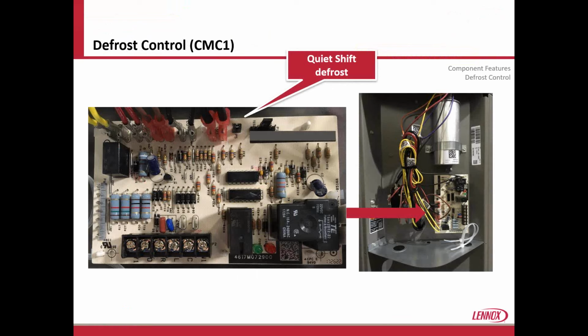All right, so our standard time and temperature board: all of our other units, including our package heat pumps, use a standard time and temperature control that you're used to out in the field. We have a quiet shift feature on it from the factory default, on pin jumper number 5. The jumper is in place, and that gives you a delayed defrost, a quiet shift type of operation. We have about a 30-second delay between the compressor shutting off and the reversing valve shifting, and then when it cranks back up, so that you don't get everything happening at one time and get that big noise.